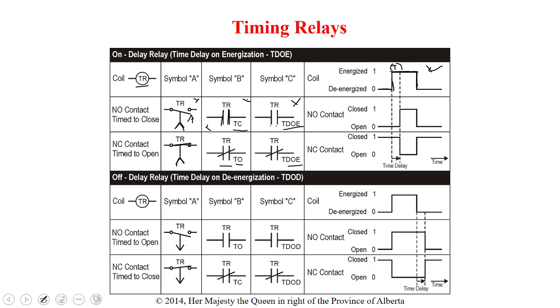Now we also have time delay on de-energization contacts. In that case, here's the little graph right here of when we energize the coil. It gets energized, and when it's energized, immediately the contacts will change state with it. When I de-energize the coil right here, the contacts don't go back to their normal state until after the given time has elapsed that we set into the timer. So that's what we call a time delay on de-energization. The contacts would keep their energized state until the time has elapsed after the coil's been de-energized.